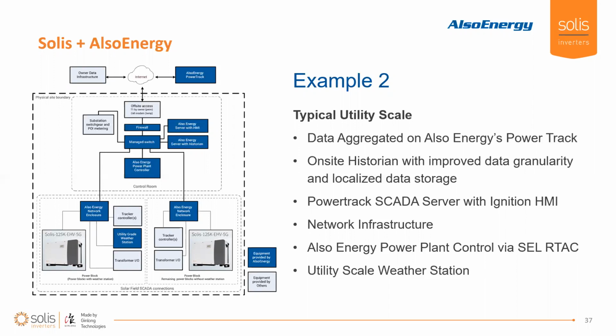We'll also use an AlsoEnergy power plant controller built on the SEL RTAC frame. From there we can execute plant control commands: voltage regulation, real power limiting, telemetry response from the utility, etc. We also coordinate with the substation and switchgear at the POI to allow real-time control from the HMI, as well as collecting data for long-term analytics or metering purposes there at the POI.